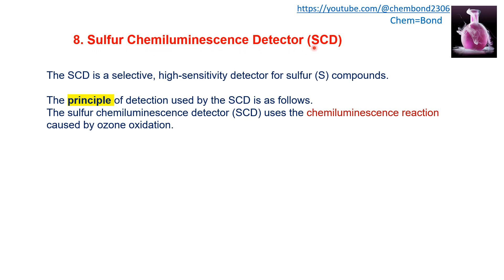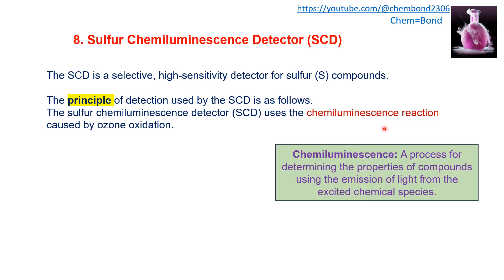The sulfur chemiluminescence detector (SCD), as the name indicates, is a selective and highly sensitive detector for sulfur-containing compounds. The SCD uses a chemiluminescence reaction caused by ozone oxidation as its basic principle. Chemiluminescence is a process for determining the properties of a compound using the emission of light from excited chemical species. Luminescence is the emission of light, and for this emission, the atom or molecule must be in the excited state. When it moves from the excited state to the ground state, it emits a photon.